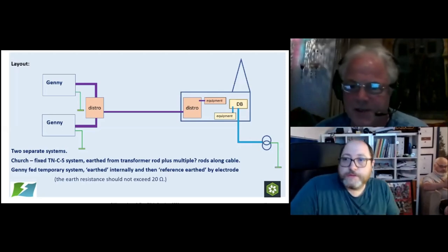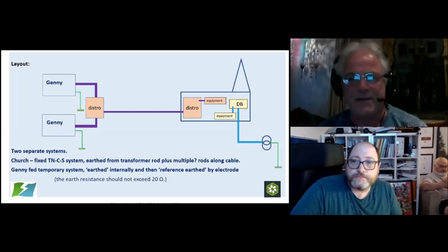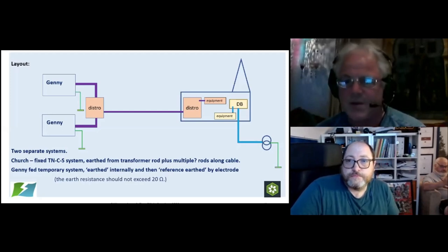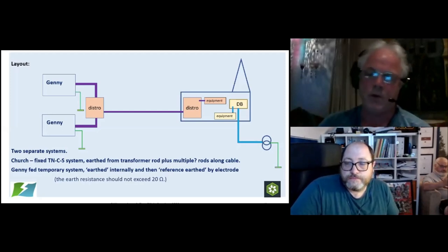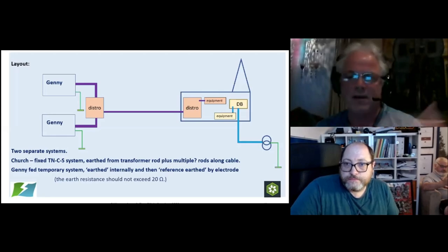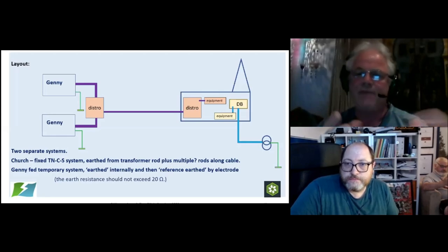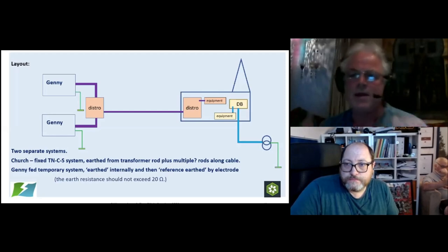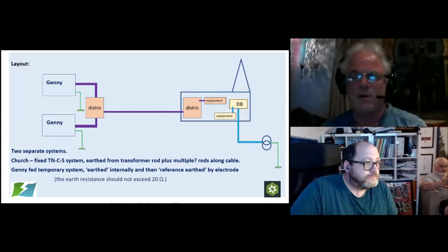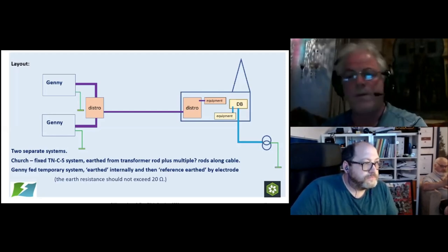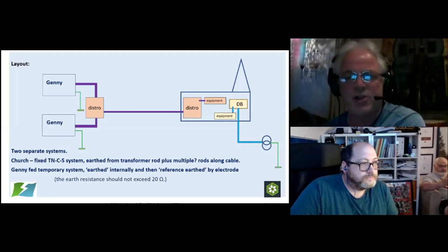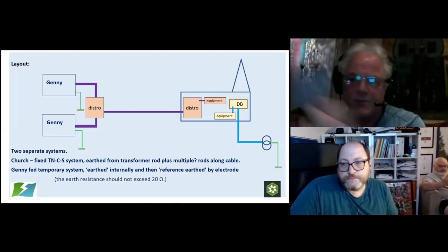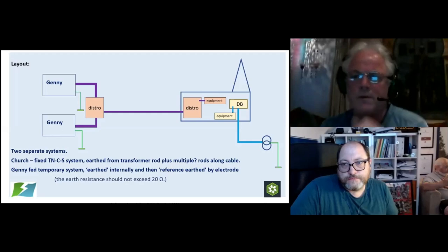Effectively bonding the two earth systems together. So you're eliminating the potential difference between the two earth systems. Remember that the equipment normally in use, if it's got metal casing like light fittings and stuff like that, if it's connected to the generator system, the light fittings, the metal casing, may be several volts removed from metalwork of the fixed installation equipment. So anybody in simultaneous contact with the two gets a little tickle off.